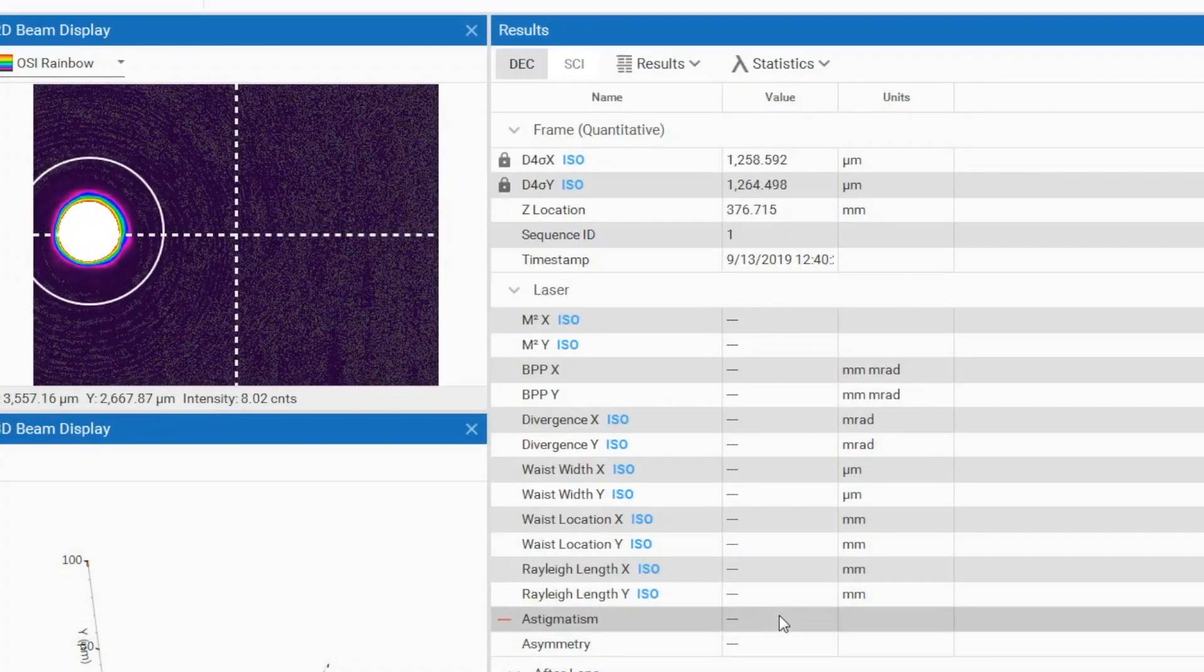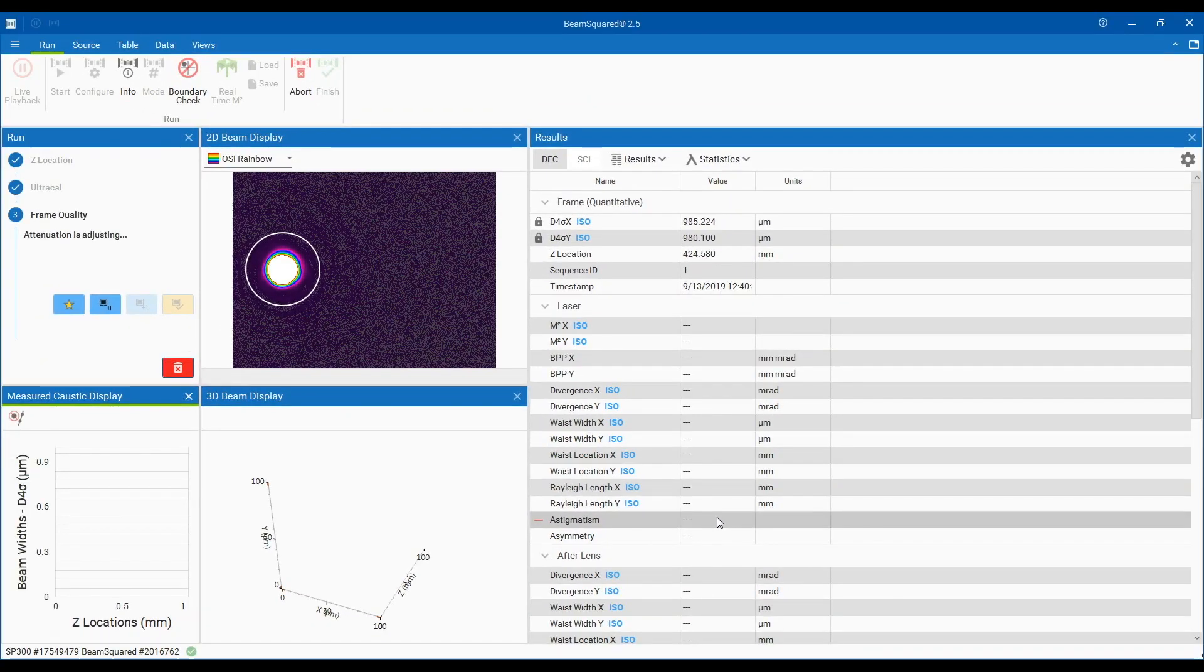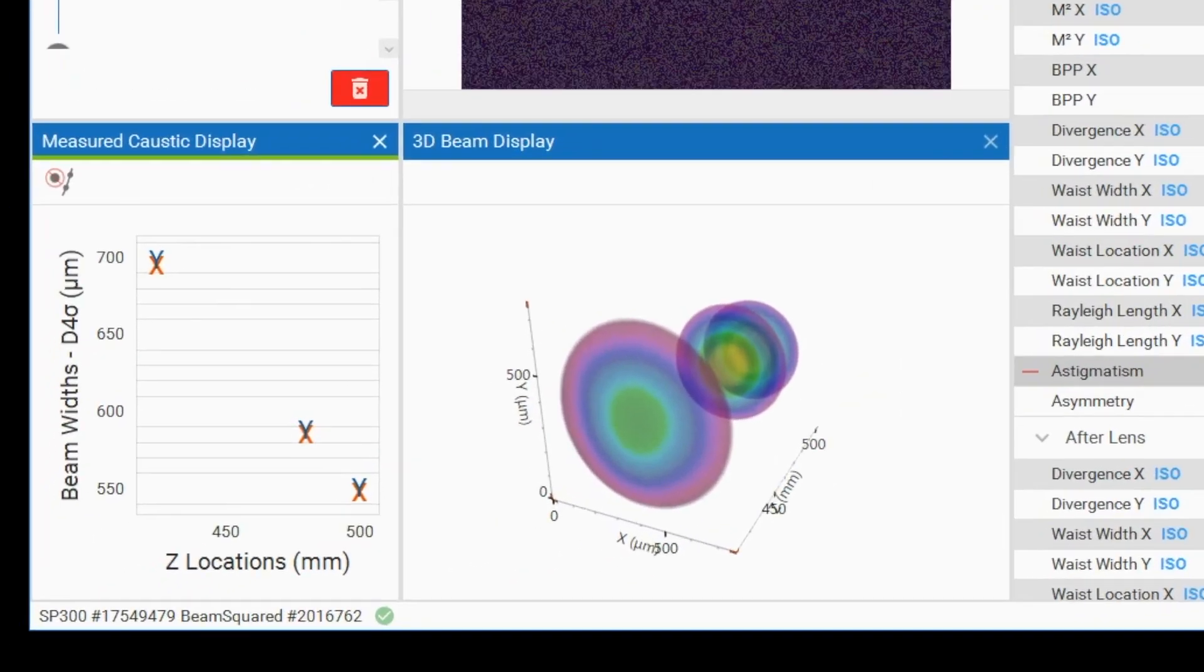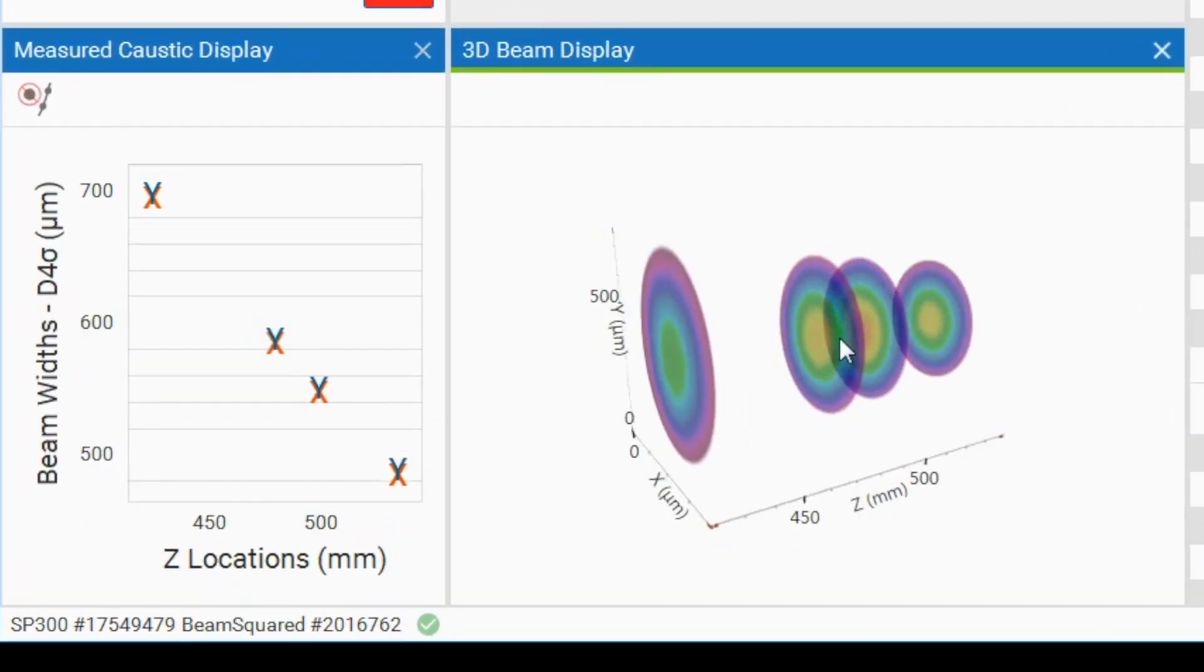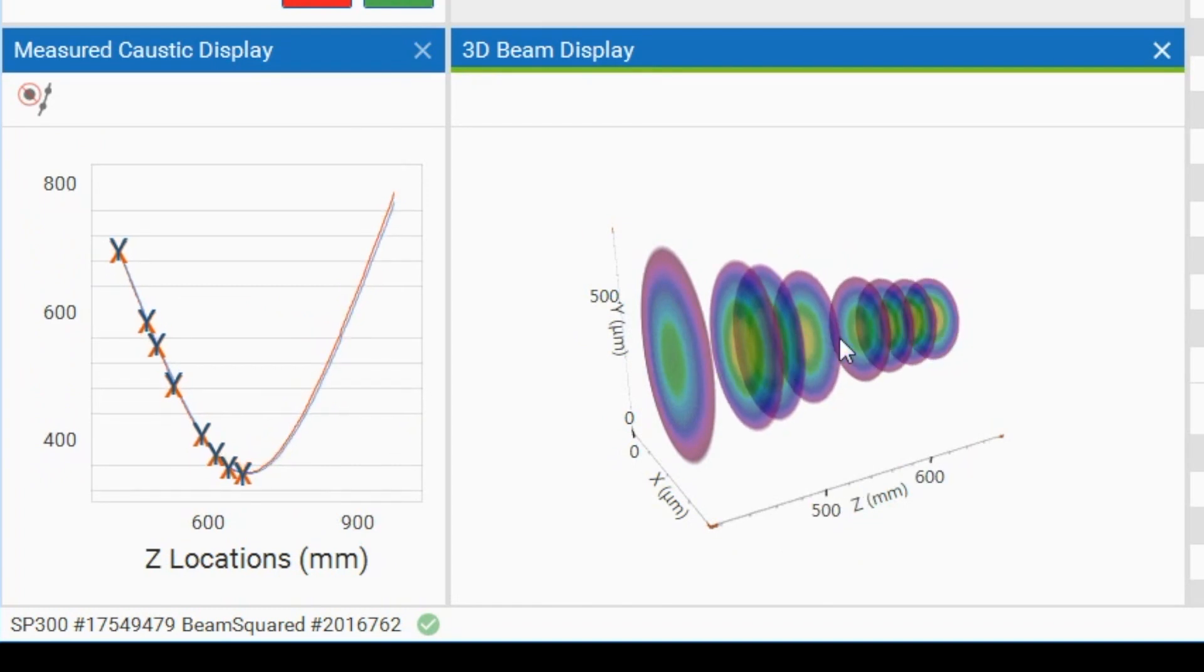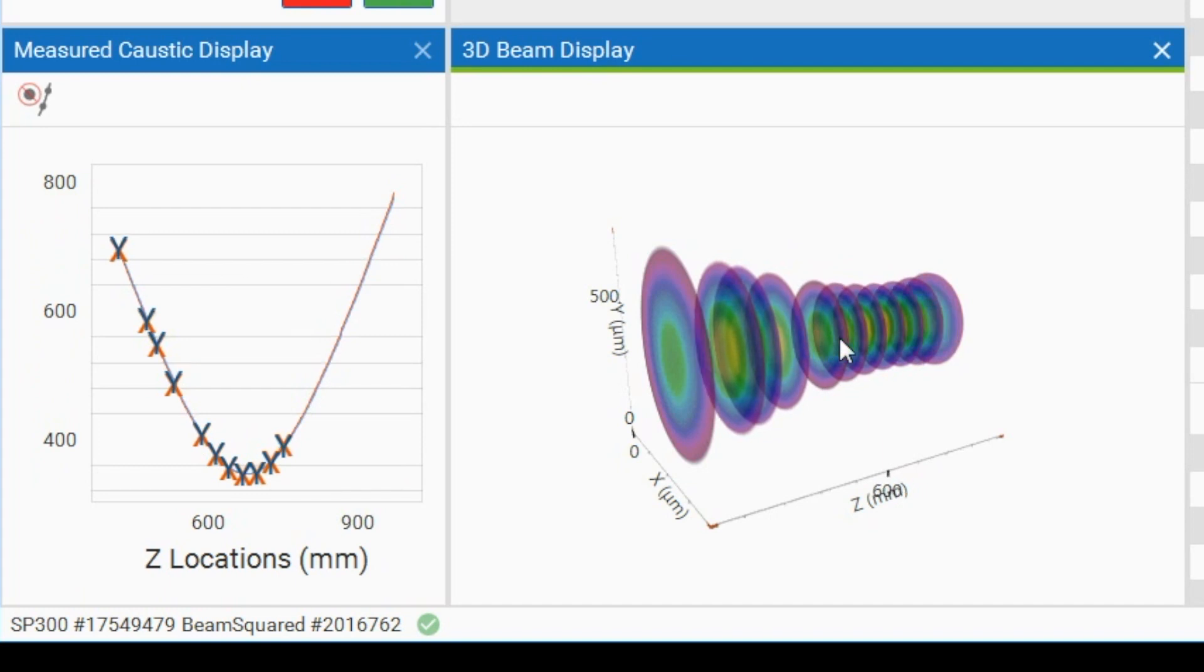The Beam Squared will then start collecting measurements at the first Z location and proceed to make additional measurements at every step. This method may also produce a measurement that satisfies the ISO standard, but the start, stop and step size parameters may need to be modified depending on the Rayleigh range of the laser under test and the lens that is selected.